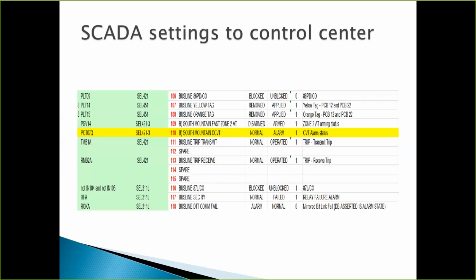Excuse me. So the final piece of this is I need to incorporate that this was the output setting for the alarm into our SCADA settings, all right? This is a relay. So if the South Mountain line, if it's in alarm, it's a 1. If it's normal, it's 0. If I satisfy that equation that we saw earlier, the logic settings, I send a high to my SCADA system, and I send that alarm. This alarm is my control center at a remote location.